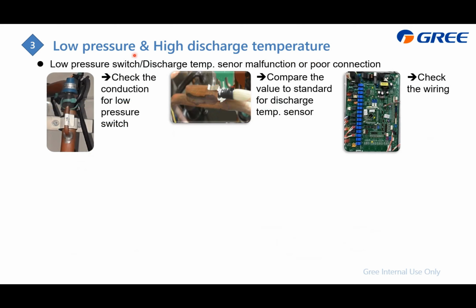And for these two, which are the low pressure protection and the high compressor discharge temperature error, first we need to check the low pressure sensor, which is this one, the conducting, and this compressor discharge sensor, also to compare with the standard value. Or if these two are okay, then check the wiring.